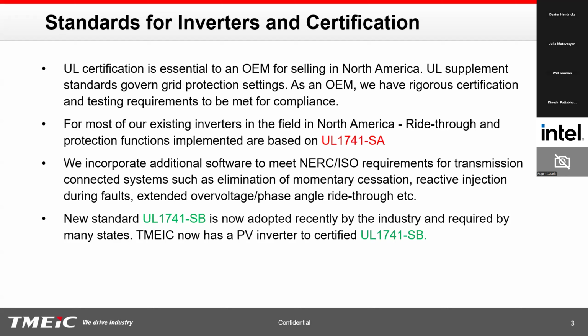And typically to meet NERC requirements or ISO requirements, we add additional software related to what the UL standard requires us to meet. Often the UL 1741 standard is based on distributed energy resources, the DER standard for distributed generation. And it has a certain requirement for ride-through curves, frequency ride-through, and so on. The old standard required us to do momentary cessation, which is not acceptable for NERC or ISO requirements. So we incorporate additional software to eliminate momentary cessation and perform other things like reactive current injection, extended voltage and phase angle ride-through capability.